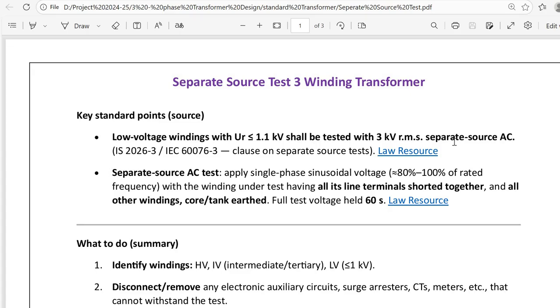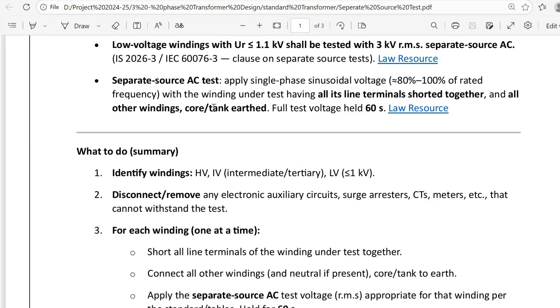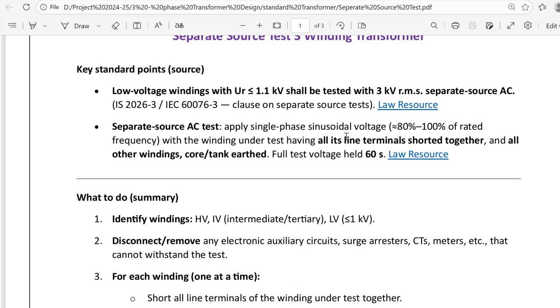This is the separate source AC test. Apply a single-phase sinusoidal voltage at 80% to 100% of rated frequency to the winding under test, having all line terminals shorted together and all other windings, core and tank earthed. The full test voltage is held for 60 seconds, which means 1 minute.